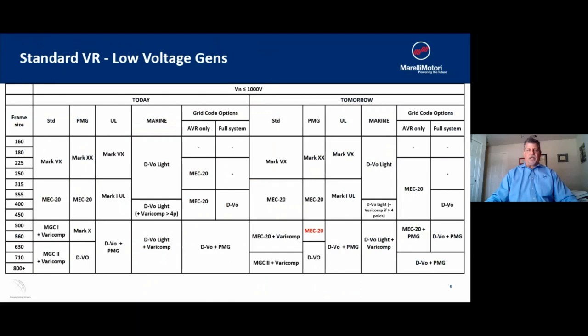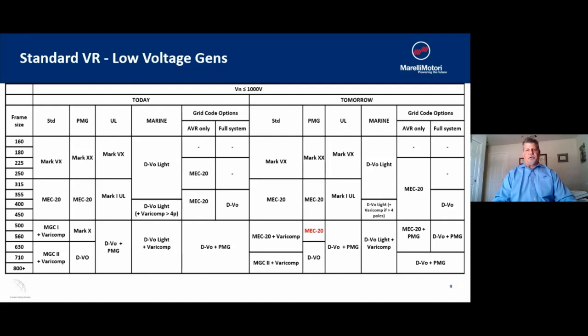Taking a look at what Marelli offers as standard voltage regulators — with stock in Atlanta and two manufacturing facilities in Italy and Malaysia — please note that for low voltage, Marelli considers basically 1,000 volts and less as low voltage. Our frame size designation on the left-hand side of the chart refers to the dimension from the bottom of the mounting foot to the centerline of the shaft. For example, a 160 frame is 160 millimeters from the centerline of the shaft to the bottom of the mounting foot; an 800 frame is 800 millimeters.